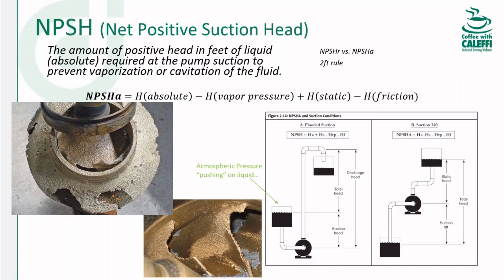So back to the impeller, when the water flashes to steam, and then when the impeller starts to increase the pressure, the pressure rises high enough so that the steam bubble collapses back to a liquid. And this is not a smooth transition. It's more like a tiny explosion or an implosion, I guess. And it's violent enough to actually chip away at the impeller, so that over time, the impeller's worn down and you actually start to lose performance. And I didn't believe it at first, but then somebody plopped one of these impellers in my hands and I said, okay, I get it now. And usually when it's cavitating, you can pretty much hear it.